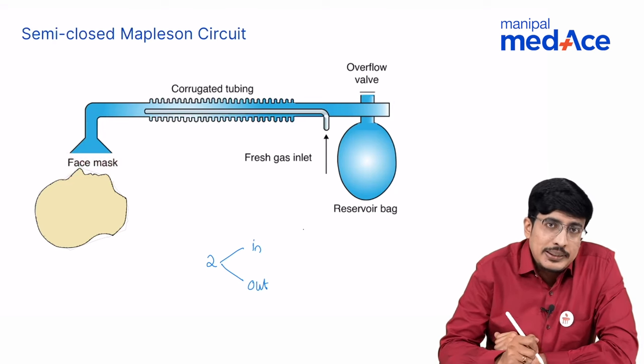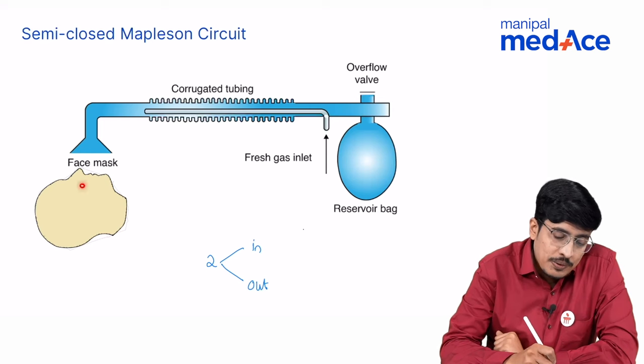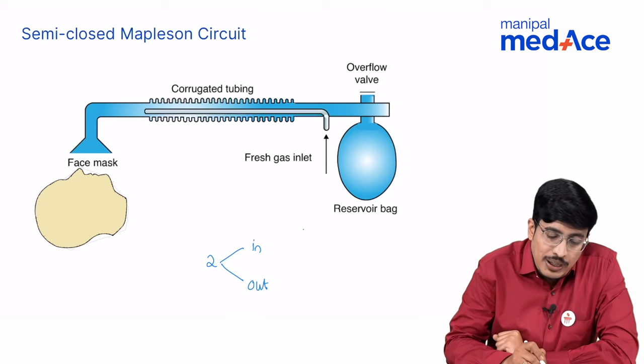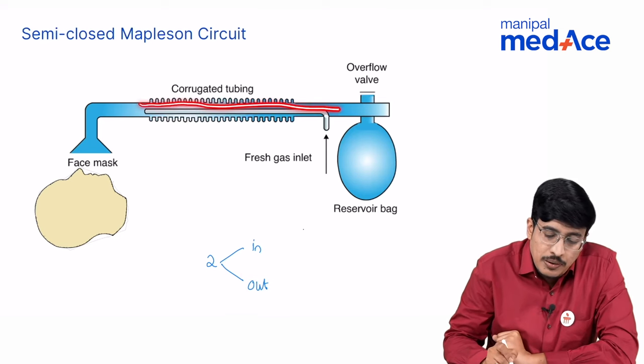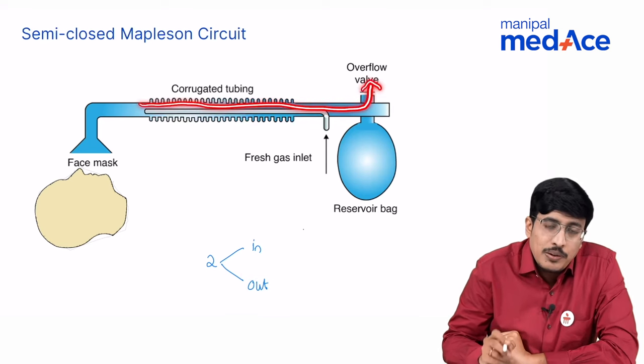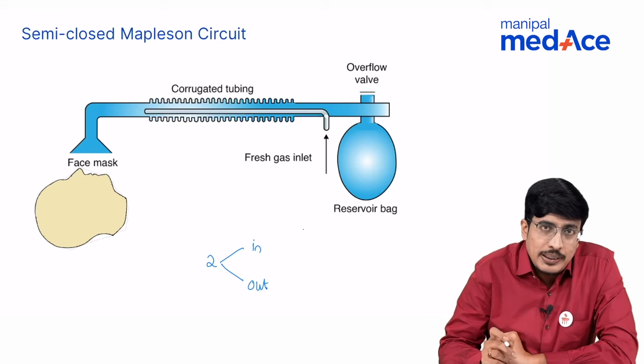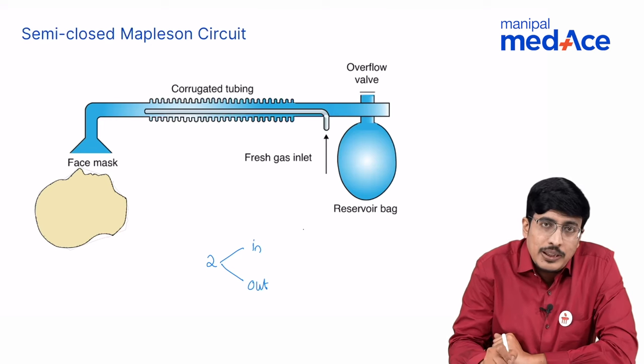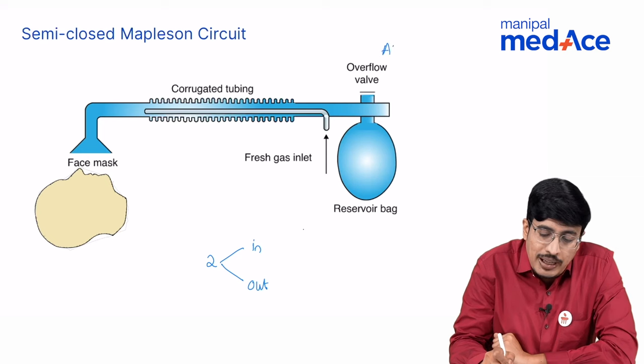Once the patient breathes and exhales the gas it would go out and get collected in this outer corrugated tubing from where it will go to the outflow valve to get excreted. The outflow valve is an adjustable valve. You can adjust the pressure by rotating a knob. It is called as the APL valve.